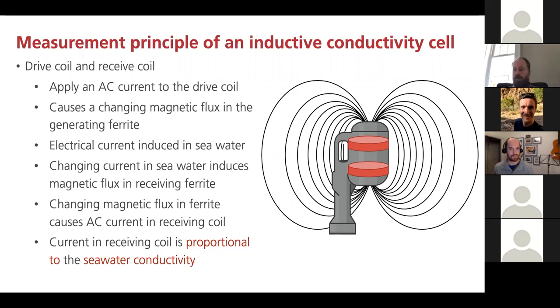of that wire loop. The wire loop isn't very interesting, but if you put a calibrated resistance in it, or resistor, particularly one that doesn't have any dependence on temperature, this is a very elegant way of checking the calibration. And in fact, it's part of how we assess the linearity of the cell in the factory itself when we're building these.